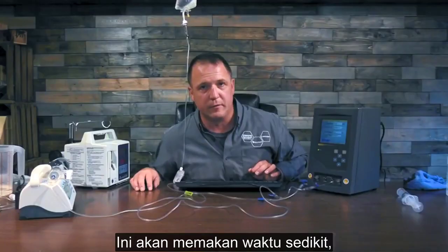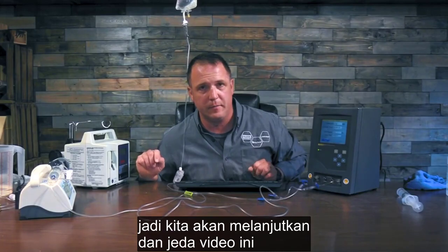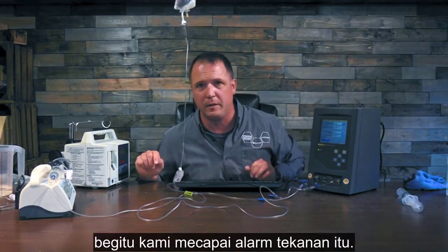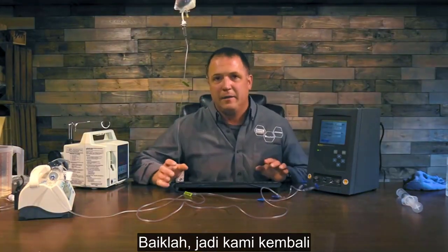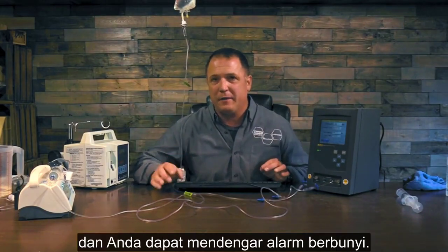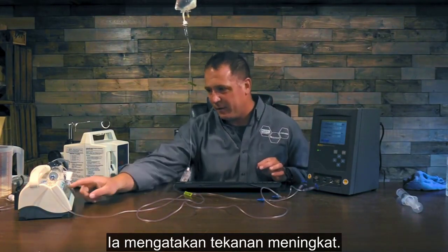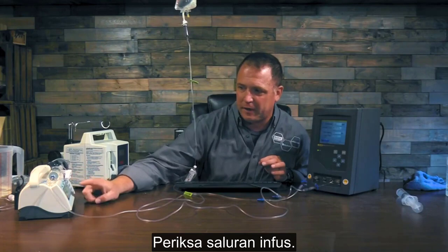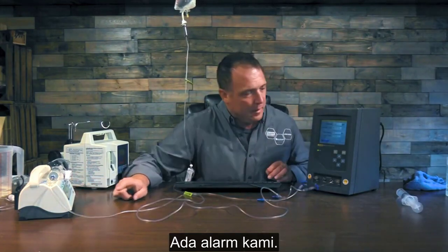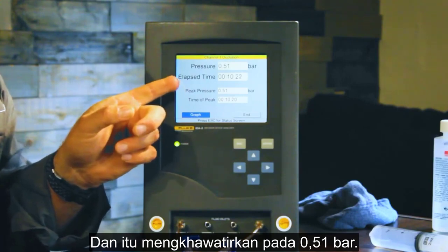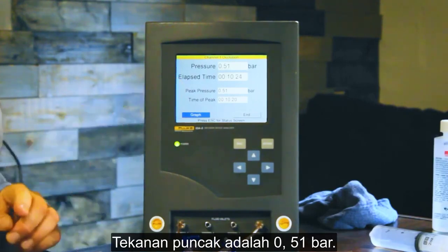It's going to take a little bit, so we're going to pause this video, and we'll come back one last time once we hit that pressure alarm. All right, so we're back and you can hear the alarm going off. It says the pressure is increasing, check infusion line. So there's our alarm, and it alarmed at 0.51 bar. The peak pressure is 0.51 bar.